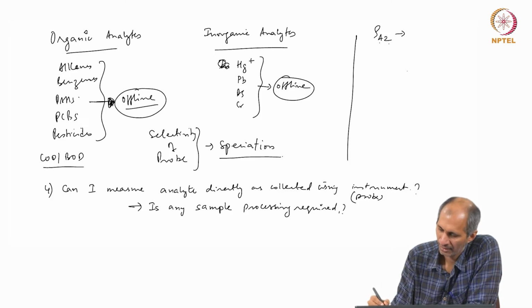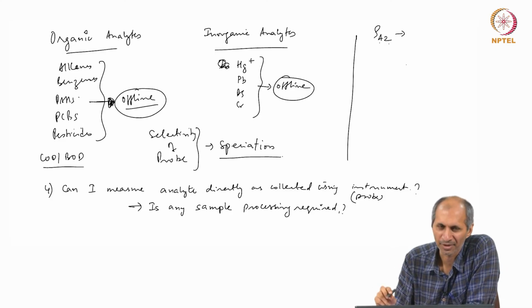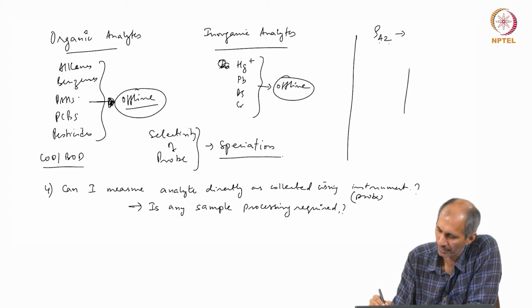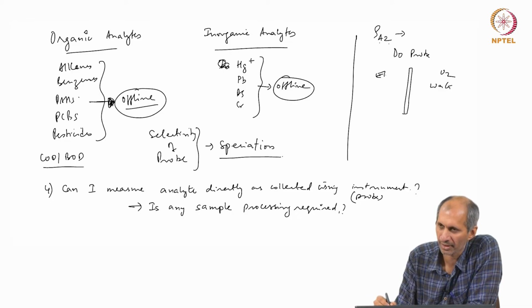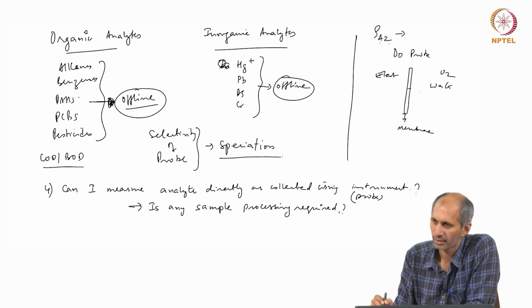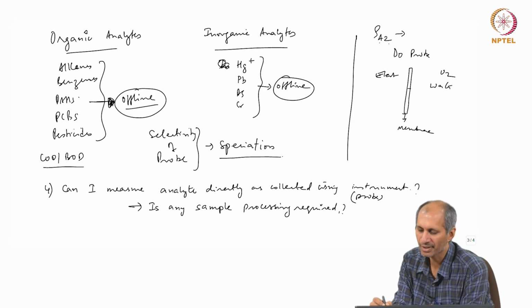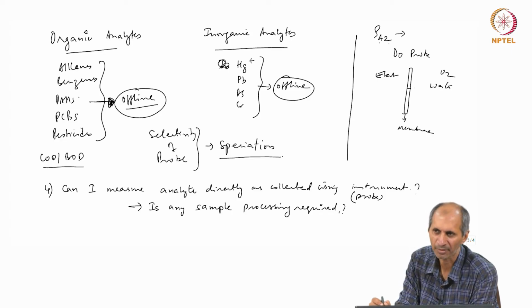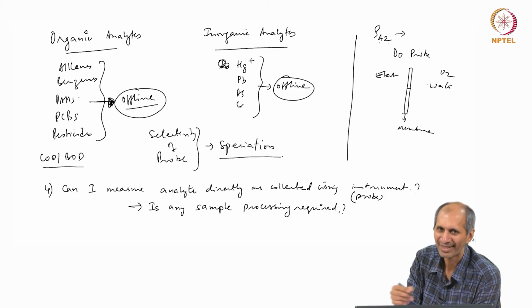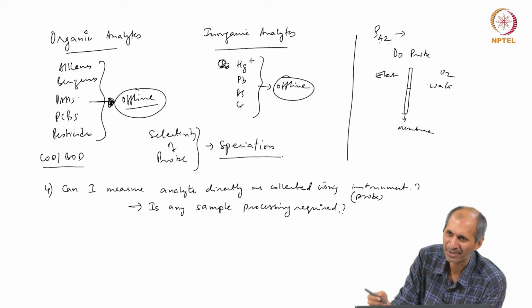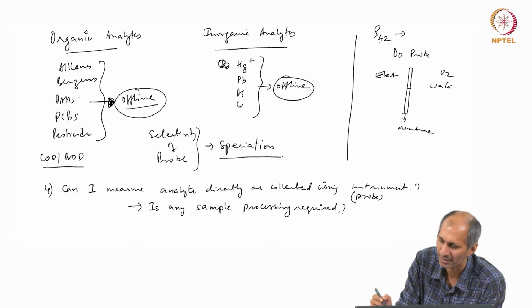Let us take the case of the dissolved oxygen probe. It's even more interesting. If you look at the DO probe, it's the same electrolytic cell. It's looking at oxygen in the water, and on this side is some electrolyte. The oxygen has to diffuse through the membrane. There is a membrane here. When the oxygen moves through, some potential difference is created and that is measured. The rate of transfer depends on the concentration. So it's a membrane transport based process. Don't worry about that.